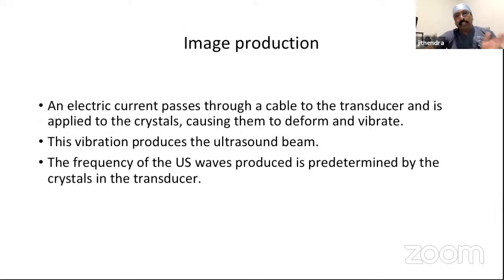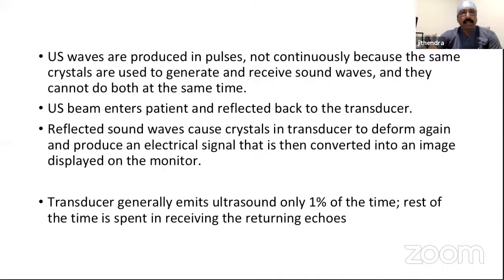An electric current passing through the cable to a transducer, as you see in the image, is applied to crystals, causing them to deform and vibrate. This vibration of the piezoelectric crystals produces the ultrasound beam. The frequency of the ultrasound waves produced is predetermined by the crystals in the transducer. So you have transducers of different frequencies. It's not continuous waves which are produced, but pulses. Because the same crystals are used to generate and receive sound waves, and they cannot do both at the same time, once it emits, it has to come back.